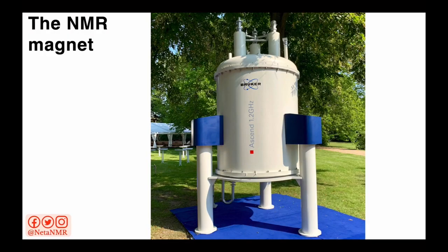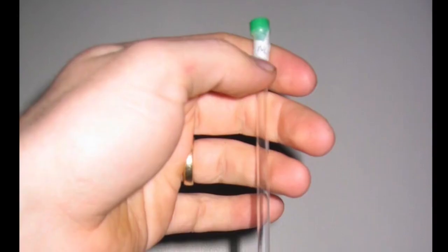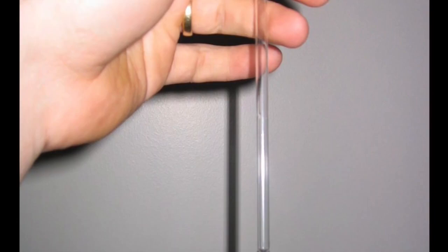First, usually in NMR, our magnets stand vertically, and the sample, which is much smaller than the human being, is placed in the magnet from above or from below the magnet. Second, the magnets we use in research usually have higher magnetic fields than those used in hospitals. And third, as I hinted earlier, our samples are much smaller and they can be prepared as either liquids or solid samples. If we work with liquid samples, we hold the samples in these kinds of tubes, and that's called solution state NMR or liquid state NMR.